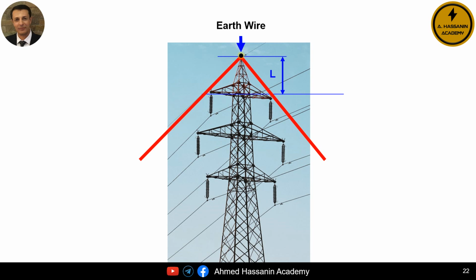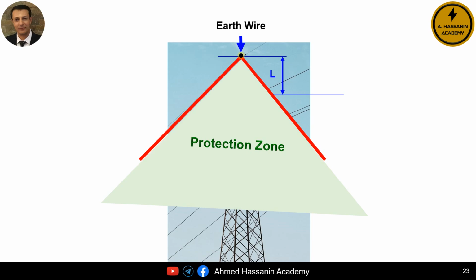From this, we understand that all the conductors, phases, or insulators located below the red lines are within or inside the protection zone. Or more precisely, as we see in front of us, the protection zone safeguards all the insulators and conductors of the tower before us. Therefore, if a lightning strike hits this line or this specific tower, we will notice that the earth wire, also called the shield wire or ground wire, is able to protect all the conductors and insulators, as clearly shown in the image before us.